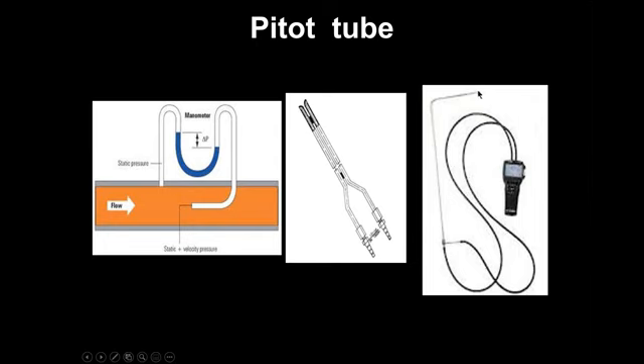Now in this also, there's a tube, and there are 2 tubes, one in another, which you can see from these 2 things coming out. It will again in the same way measure the static and total pressure, and the difference will give you velocity pressure, which will again be calibrated with a digital pressure gauge or any digital system to give you velocity directly, or it will give pressure. You can use the pitot tube formulae to calculate the flow.